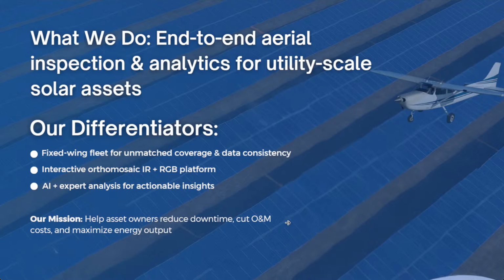Once we develop the pictures and everything is stitched together, we're able to use computer vision, like AI and machine learning tools, to quickly analyze and spot out any of the faults. Traditionally, we would have people just hand go through line by line in the array just to see this row has an issue.